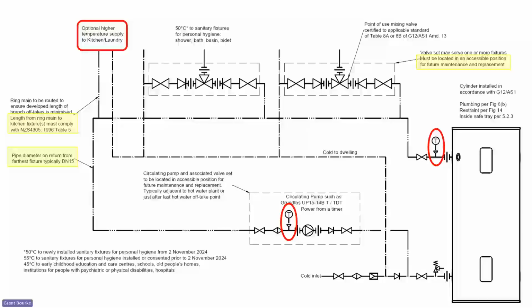Typically the return pipe's going to be 1/2 inch or thereabouts, but we'll go into the sizing of that in a bit more detail in a few minutes. We also need a non-return on the ring main return. If we don't have this, when I turn a fixture on, I run the risk of cold water entering back up the ring main and out the fixture, and the pumps are only small and they are not going to overcome to any close degree the water pressure that you've got in the system. So we need a non-return to stop the cold incoming water taking a shortcut.